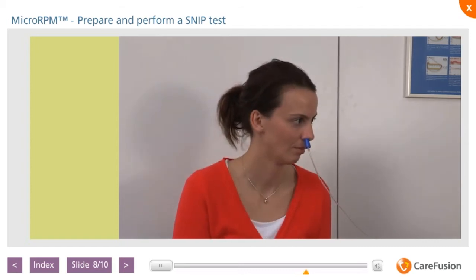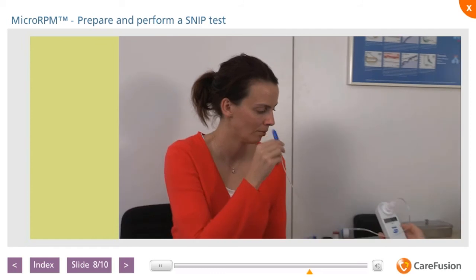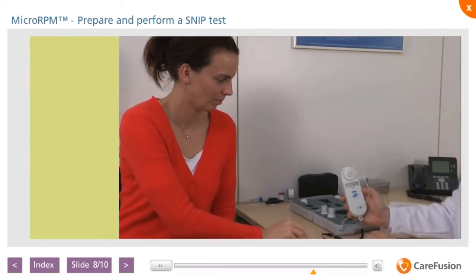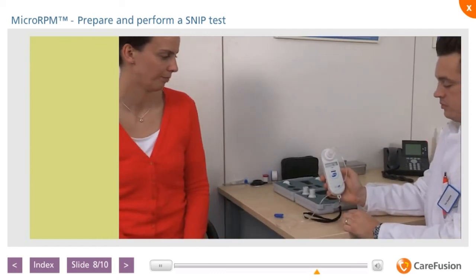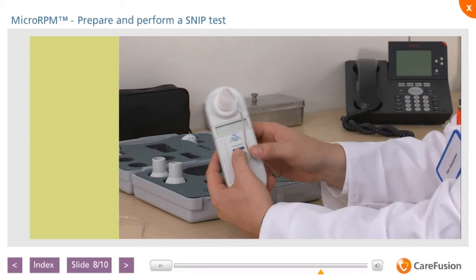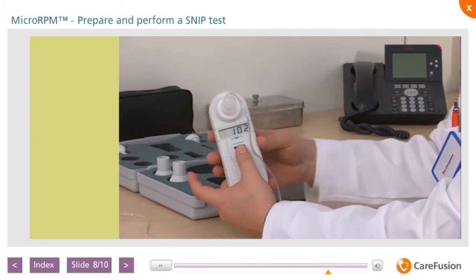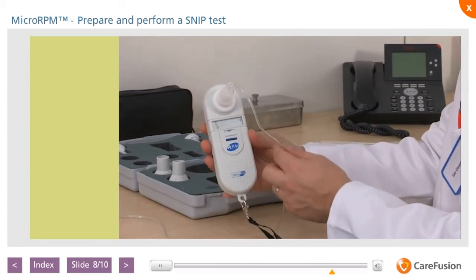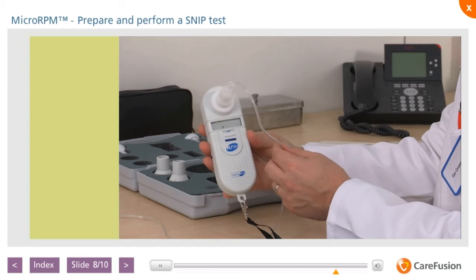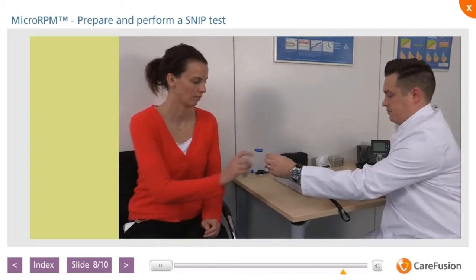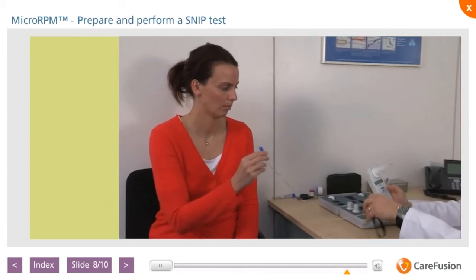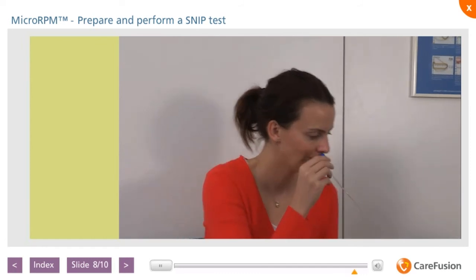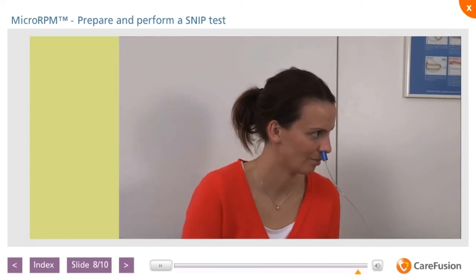The results will be displayed in centimeters of water on the display. Between tests, the nasal probe should be removed from the patient's nostril, the unit turned off, after which the slide switch should be pushed back to the SNIP position to enable the unit to auto-zero. Once the unit has auto-zeroed, the nasal probe should be placed back into the patient's nostril and the maneuver repeated. Ideally, 10 measurements should be performed, with the highest taken as the value achieved.